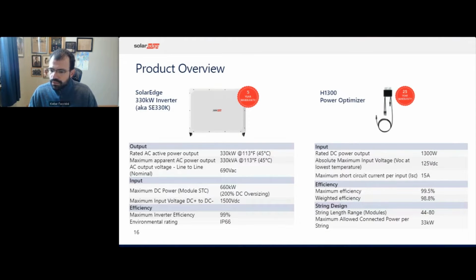For the 330kW and also for the H1300 optimizer. Okay. On the inverter side, the 330kW goes up to 113 Fahrenheit, which is 45 Celsius, and there is no derating up to this temperature level. The inverter can actually operate up to 60 Celsius, but between 45 and 60 Celsius there is a derating. 690 volts AC output voltage, improving inverter power density and reducing AC power losses.